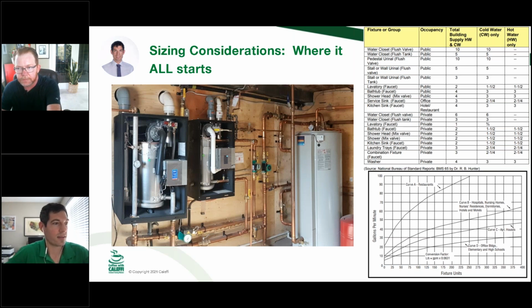So I think two slides ago, they started with a bunch of different sizes of cinder blocks, and they said, okay, what water heaters can we put on top of these so they'll all line up at the top there? So if you want to turn back the clocks, Winston Churchill had just become Prime Minister of Great Britain. That's when these Hunter's curve calculations started. So a lot of what we do in plumbing is still rooted in these Hunter's curve calculations that were done 80 years ago. And what we're finding, the deeper that we look, is that they are oversized for what we're doing with modern plumbing, as kind of a general statement.